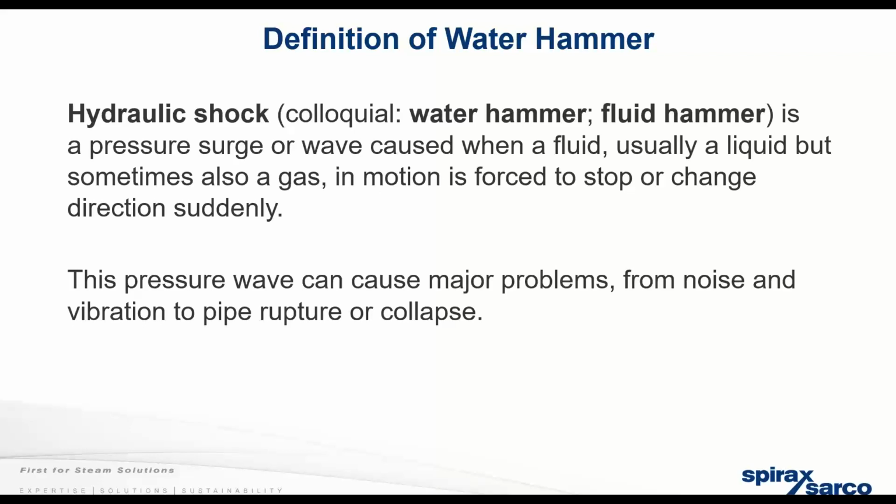All right. So WaterHammer. When I was thinking about doing this presentation, I did what everybody else does. I Googled it. What is WaterHammer? Basically, it's a hydraulic shock that causes waves, noise, and damage in our piping system, and that's just what it is. We're going to talk about WaterHammer only in steam systems, not so much in water systems today.